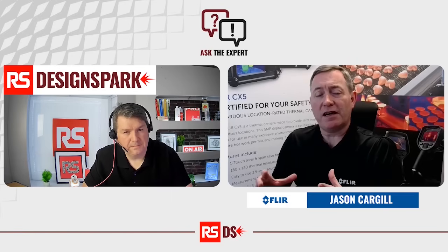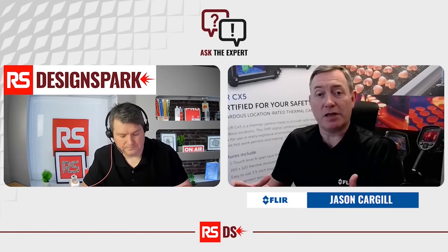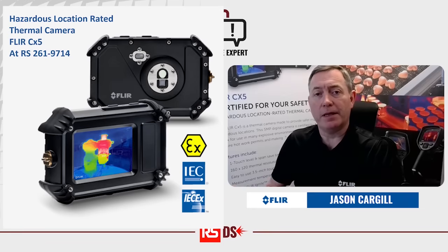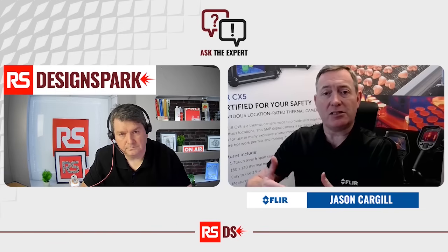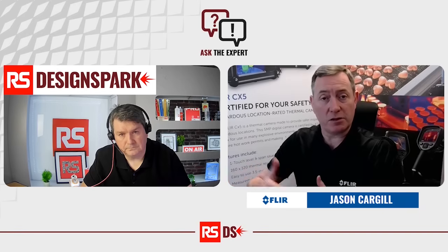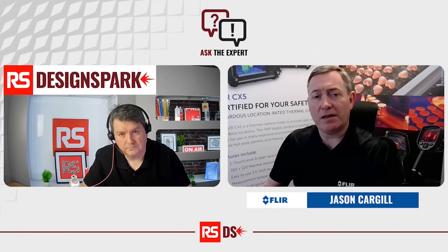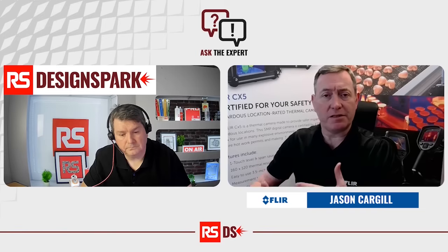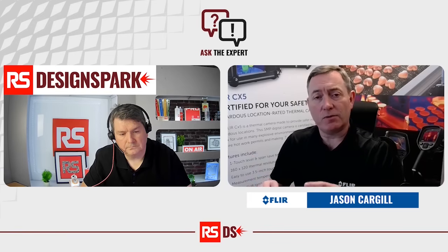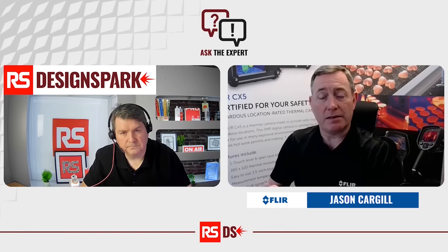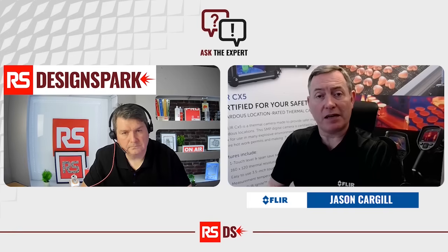So the CX5 is our first step into the Ex rated thermal camera. We have a lot of users, for example, petrochemical facilities, a lot of industrial areas. They'll have their Ex zone rated areas where they have to use particular types of equipment. And we've now launched a product which, it's not intrinsically safe, because that would mean a difference in materials and using certain materials for production. But what we've done is we have created a restricted breathing method case, which encloses the Cx5 camera.